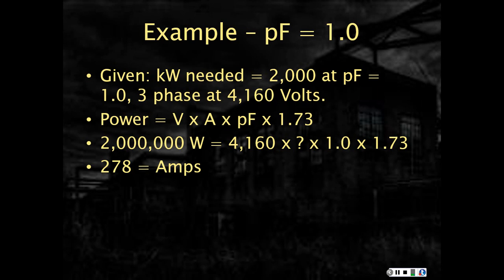Now you should remember that to get 2,000 kilowatts of power, that's real or working power, I need 278 amps. Now remember, amps set the size of the wire. Now that's with a power factor of 1.